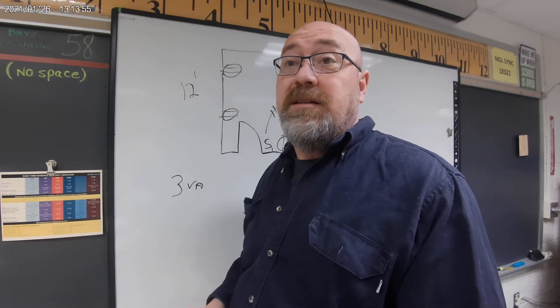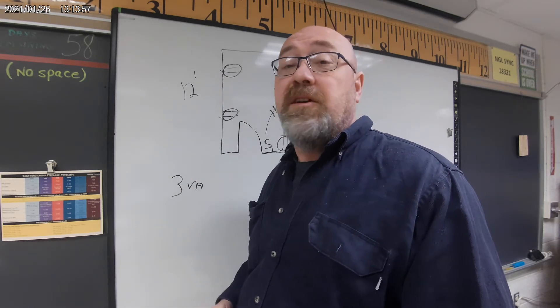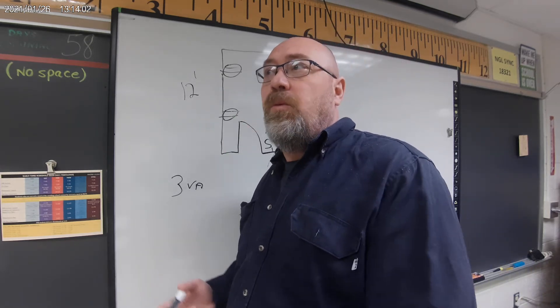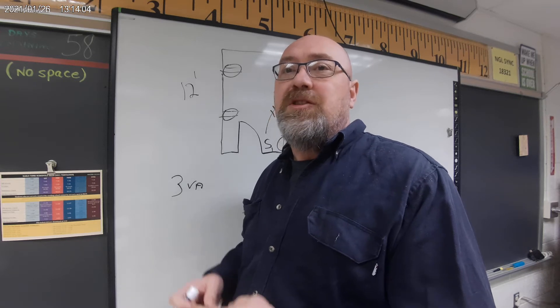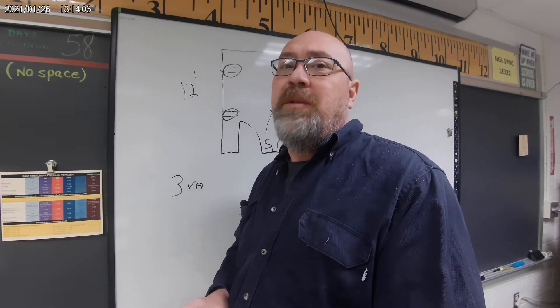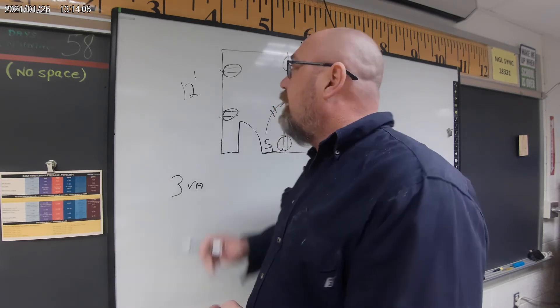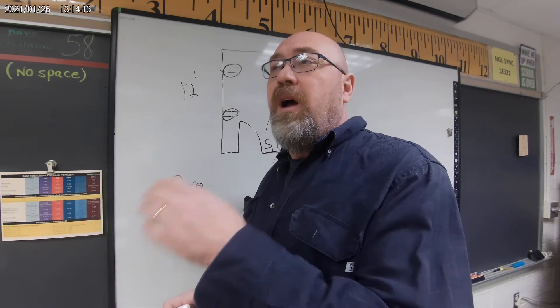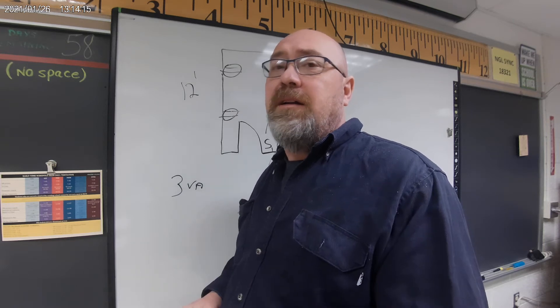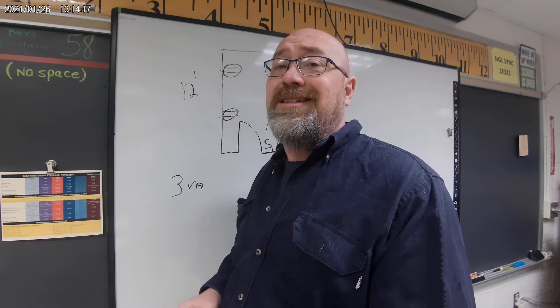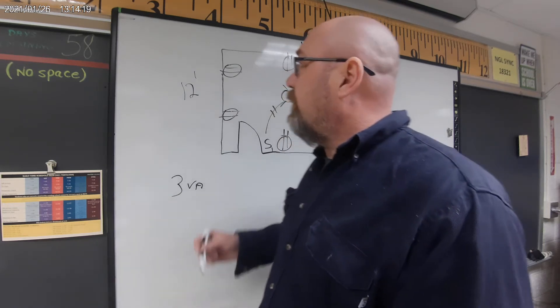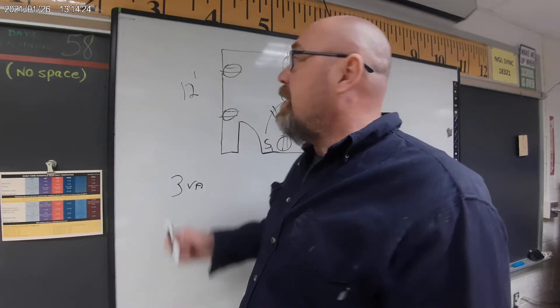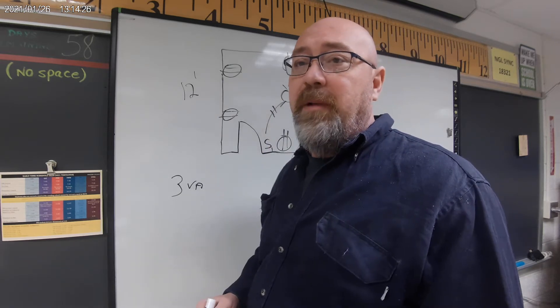When I have an outlet with nothing plugged into it, it's technically not drawing any power. Plug a lamp with a 60 watt bulb, it's drawing 60 watts. Plug a blow dryer, now it's drawing 1500 watts. It's always changing, so we need a number. They give me a calculated number of three volt amps per square foot. This bedroom is a 12 by 12 bedroom.